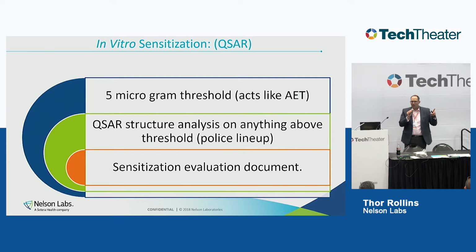It's bad stuff. But 2, these tests are not sensitive. There's been a lot of data out there to show that something that is a sensitizer, like nickel, for example, which people use in medical devices, even high levels of nickel won't fail in the guinea pig max. So it's not a very sensitive test. And this glutathione assay is actually a little bit more sensitive than the maximization test itself. Any other questions before we move on?